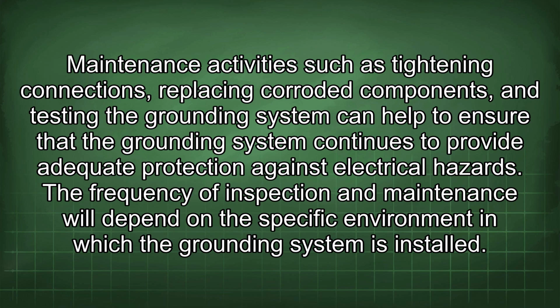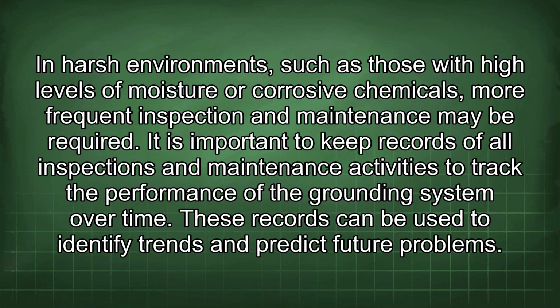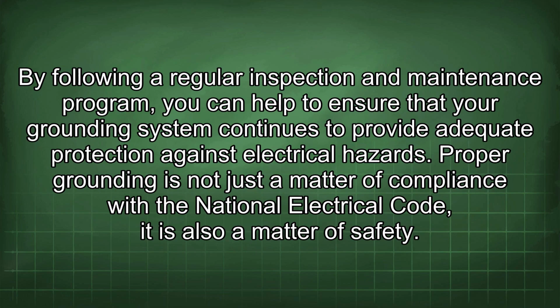The frequency of inspection and maintenance will depend on the specific environment in which the grounding system is installed. In harsh environments, such as those with high levels of moisture or corrosive chemicals, more frequent inspection and maintenance may be required. It is important to keep records of all inspections and maintenance activities to track the performance of the grounding system over time. These records can be used to identify trends and predict future problems. By following a regular inspection and maintenance program, you can help to ensure that your grounding system continues to provide adequate protection against electrical hazards.